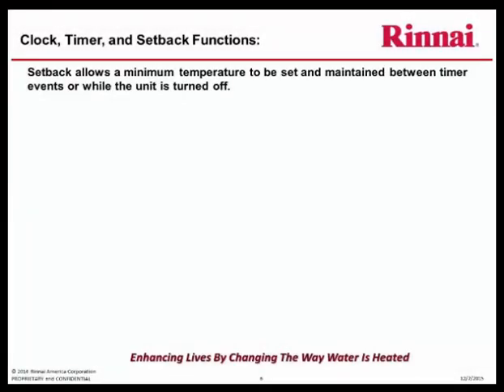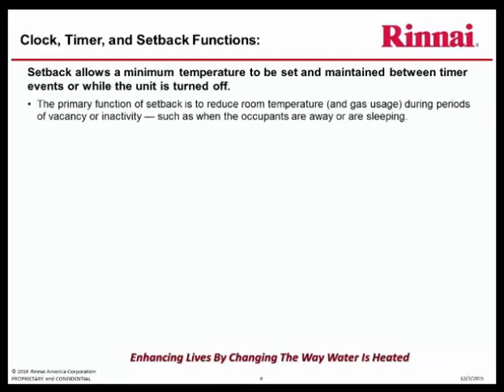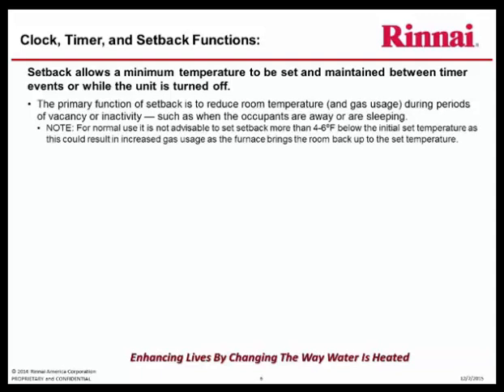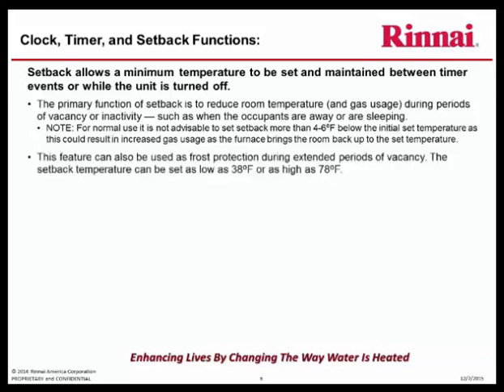Setback allows a minimum temperature to be set and maintained between timer events or while the unit is turned off. The primary function of setback is to reduce room temperature and gas usage during periods of vacancy or inactivity, such as when the occupants are away or are sleeping. Note: for normal use, it is not advisable to set setback more than 4 to 6 degrees below the initial set temperature, as this could result in increased gas usage as the furnace brings the room back up to the set temperature. This feature can also be used as frost protection during extended periods of vacancy. The setback temperature can be set as low as 38 degrees Fahrenheit or as high as 78 degrees Fahrenheit.